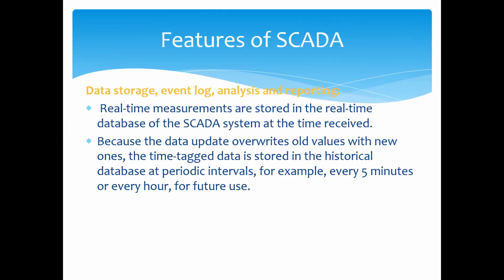Data storage, event log, analysis and reporting. Real-time measurements are stored in the real-time database of the SCADA system at the time received. Because the data update overwrites old values with new ones, the time-tagged data is stored in the historical database at periodic intervals, for example every 5 minutes or every hour, for future use.